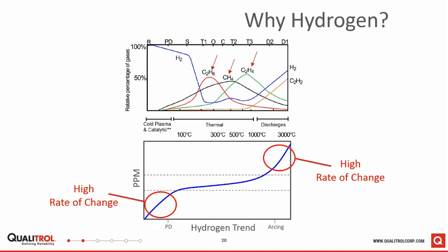The other part is that hydrogen is the smallest molecule and will leak out of the transformer faster than any of the other gases. So typically, if hydrogen was created six months ago and there was a significant amount of free hydrogen in the transformer, you might take a DGA today and find that there's no free hydrogen in the transformer, but you do see the methane, ethane, or ethylene in the oil. And it's not that the hydrogen wasn't created, because if the hydrogen wasn't created up front, you wouldn't have the methane, ethane, and ethylene.